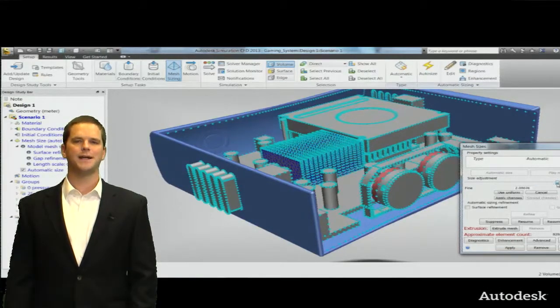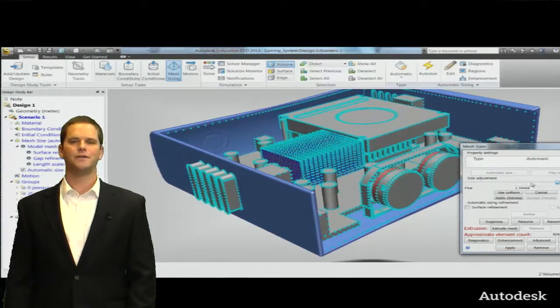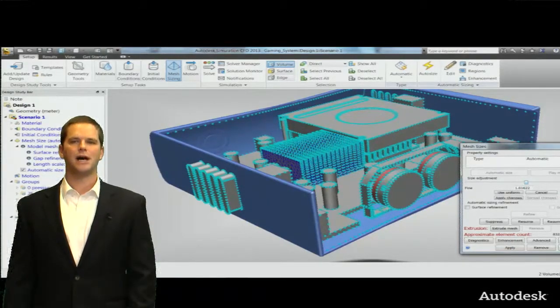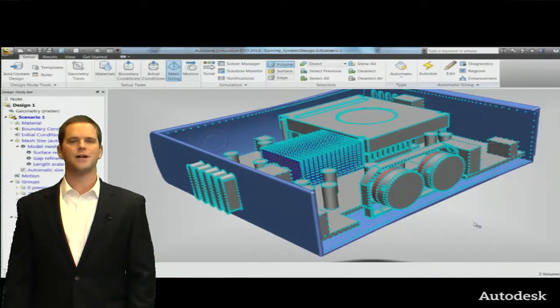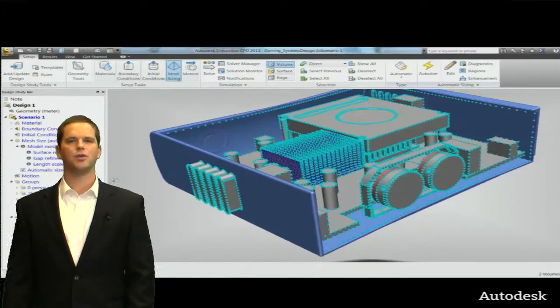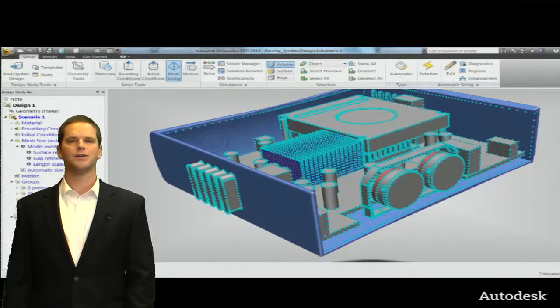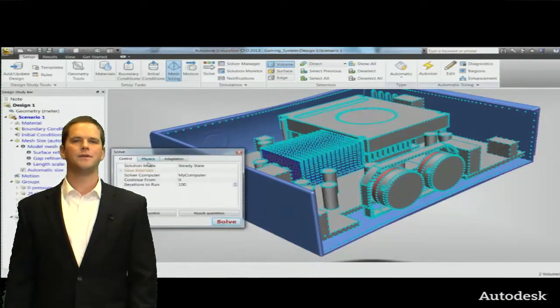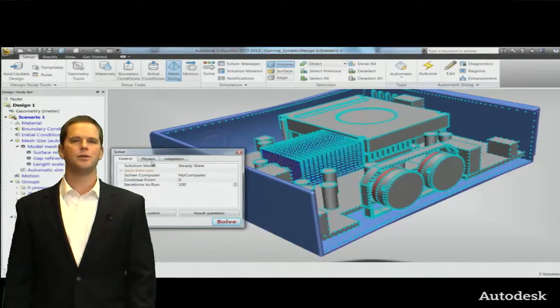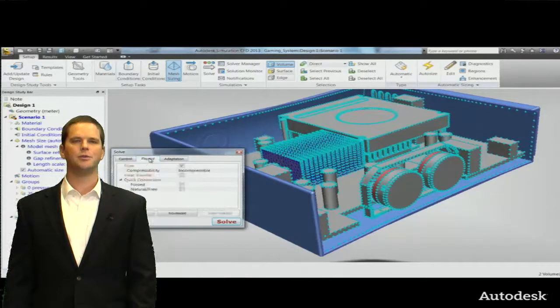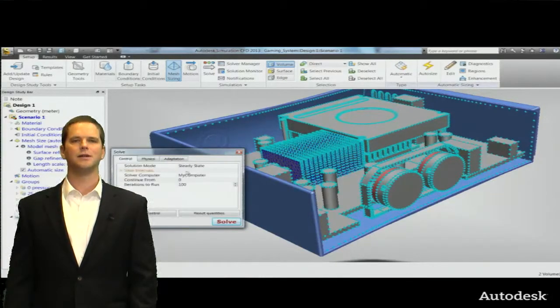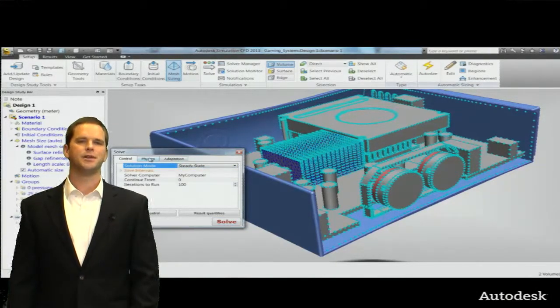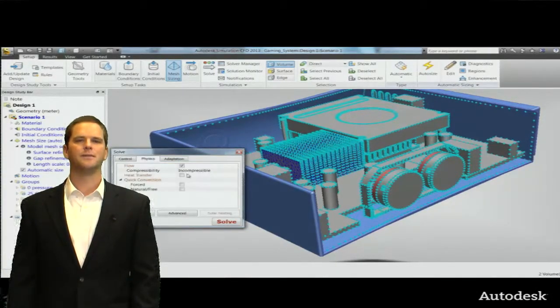We did a quick mesh preview on the heat sink which we saw and one other best practice that we'll do here is to go in and actually tighten down the mesh on the fan materials. There are very high pressure and velocity gradients as we work through the fans and they're solving for the flow rate based on the fan curve. So we want a little bit more fidelity, a little bit more data there to get a better solution.